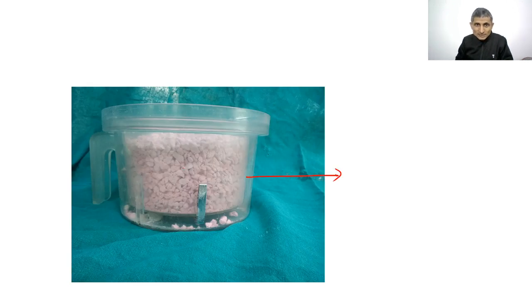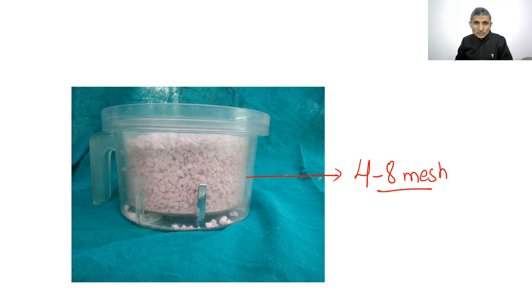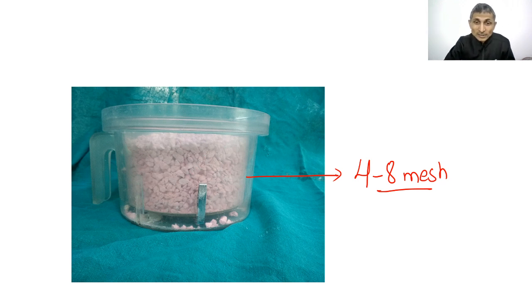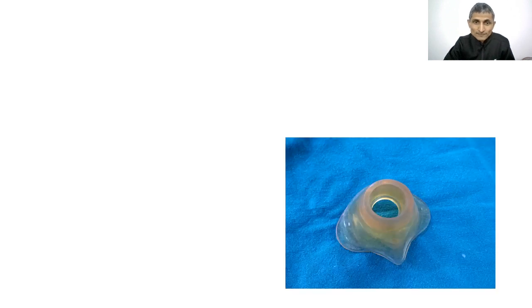This is CO2 absorbent — soda lime with indicator in a transparent canister. Its optimum granule size is 4–8 mesh. When 50–70% of the soda lime color has changed, it should be replaced. It comes in granule form, not powder, and is used for carbon dioxide absorption as part of a closed circuit.